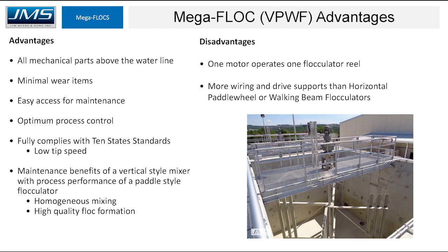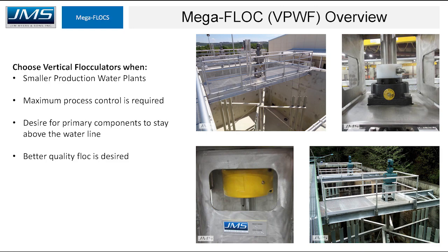The disadvantages of vertical paddle wheel flocculators are that one motor operates one floc reel, which drives up cost, and there is more wiring and drive supports than horizontal or walking beam flocculators. You might choose vertical paddle wheel flocculators for small production water plants where maximum process control is required, where components staying above the water line for easy maintenance is desired, and where the highest quality floc particle is needed.